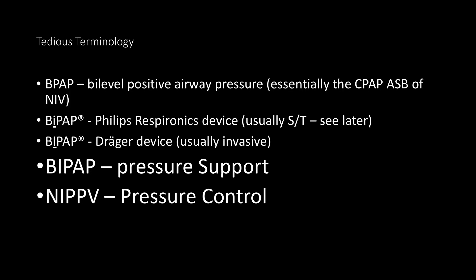Now let's talk about modes of ventilation — and I'm afraid there's quite a lot of tedious terminology here. BPAP is bi-level positive airway pressure; it's essentially the CPAP ASB of non-invasive ventilation. BiPAP with a small 'i' is a registered trademark referring to bi-level positive airway pressure in the context of a Philips Respironics device, usually used in ST mode. BiPAP with a capital 'I' is a registered trademark referring to a Draeger device and usually means invasive ventilation. In general, BiPAP means pressure support ventilation, and NIPPV means pressure control ventilation.